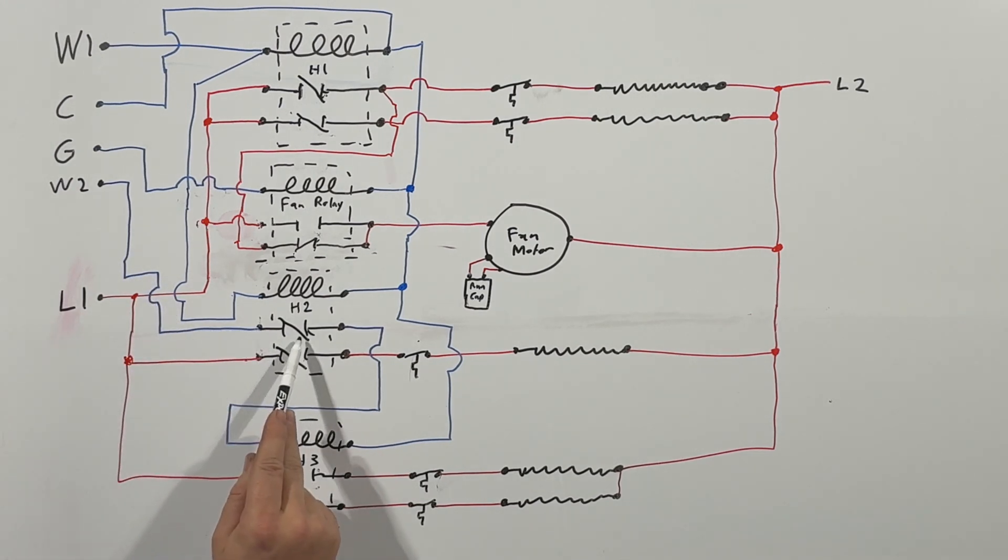Now if we call for W2, we put 24 volts and it'll travel if this is energized. It'll go through it and continue down, energize this sequencer down here, which will close these two relays and energize these heating elements over here.